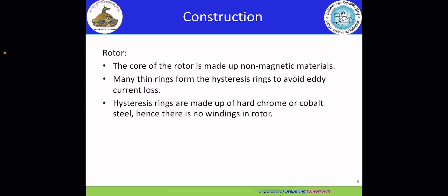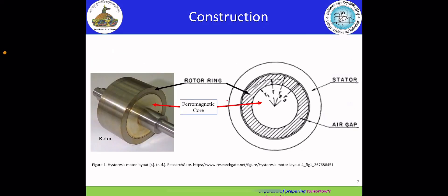Secondly, the rotor. The core of the rotor is made up of non-magnetic material. Many thin rings form the hysteresis ring to avoid eddy current loss. Hysteresis rings are made up of hard chrome or cobalt steel. Hence, there is no winding in the rotor. This diagram shows the construction of the hysteresis motor, illustrating the ferromagnetic core, rotor rings, stator, and air gap.